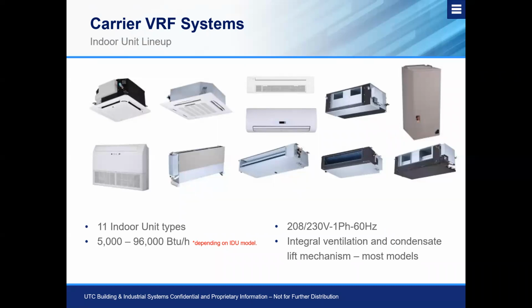Okay, we have our ducted style units, so our low static, medium static, and high static units on there. Low static, we're going to look at being about 0.2 inches of static pressure. Mid static is going to give us about 1/2 inch of static pressure. And then finally, our larger size high static unit will range from 0.8 up to 1.1 inches of static pressure. Now, of course, that's definitely something that we need to take into consideration when we're applying the unit and how many takeoffs we can facilitate to make sure that we get proper air distribution throughout the spaces we're trying to serve.